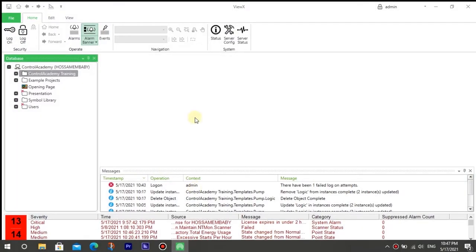In this video, we will create a Structured Text program that monitors the input states of our pumps created in the previous chapter. The program will reset the start command output when it detects that the pump running feedback is turned on after the command is issued. We will first create a new Structured Text logic program in the pump template so that each pump in the system has the reset functionality.